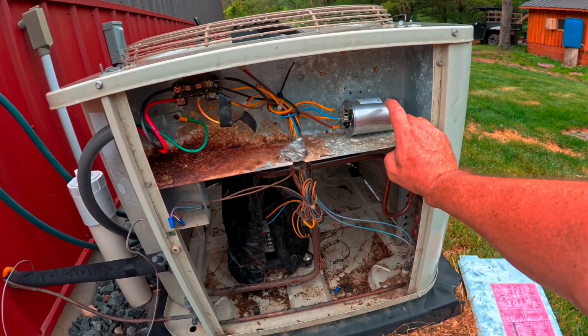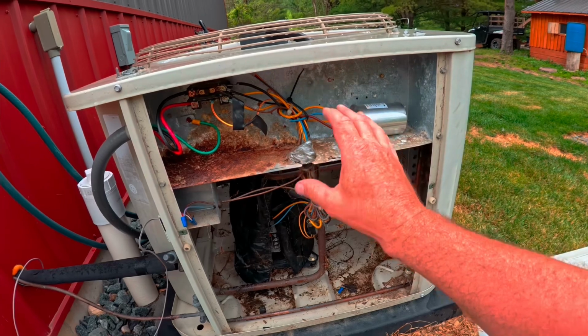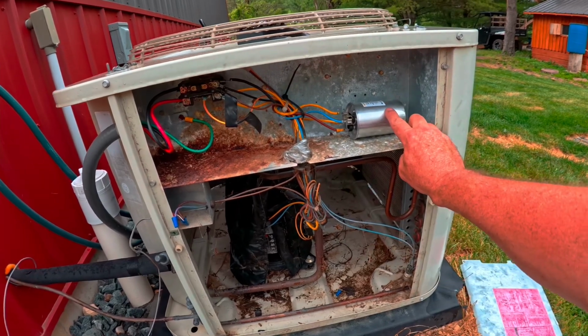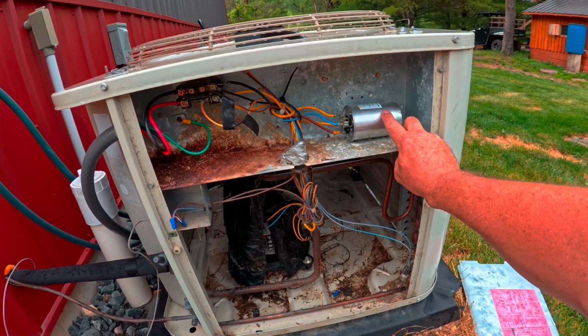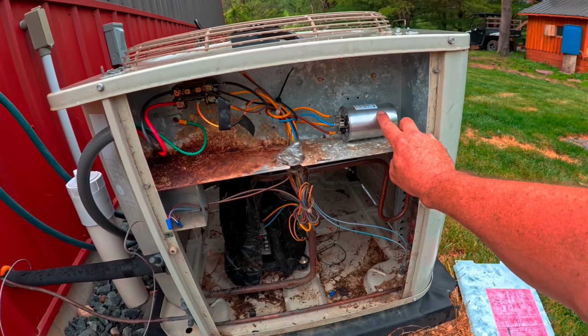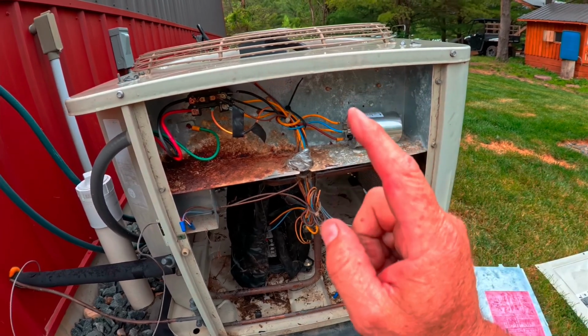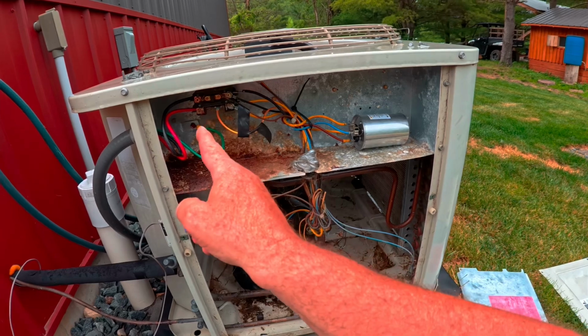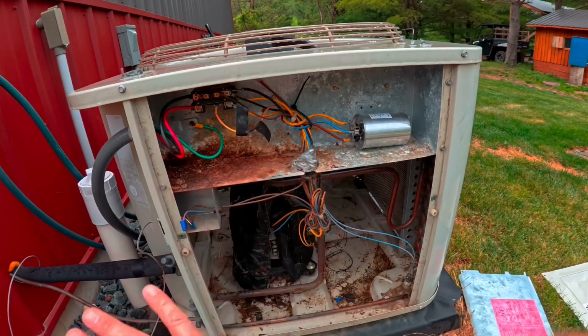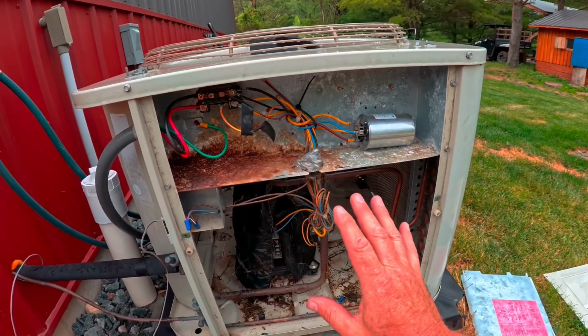Rule number 1, make sure the power is off to this unit. This thing is storing electricity. You do not want to get hit by a cap. These things will set you on your butt. Make sure the power is turned off. Verify with your voltmeter, no power, no power. Make sure everything's shut off. I cannot stress that enough.